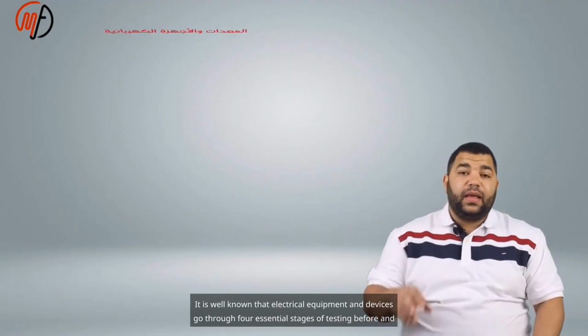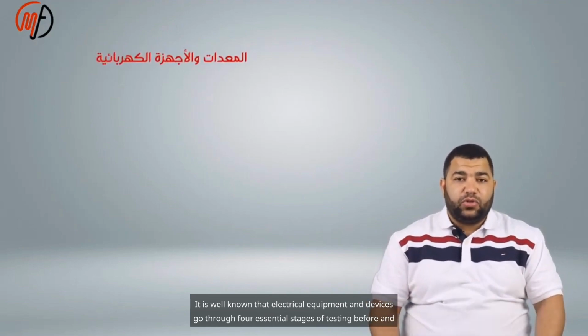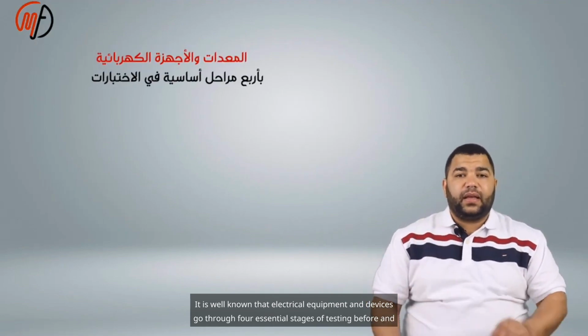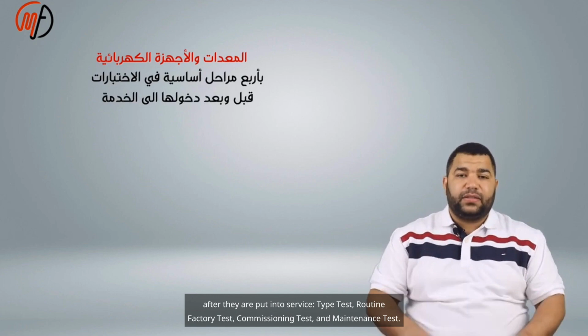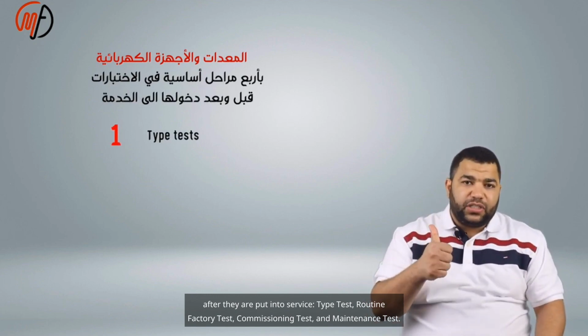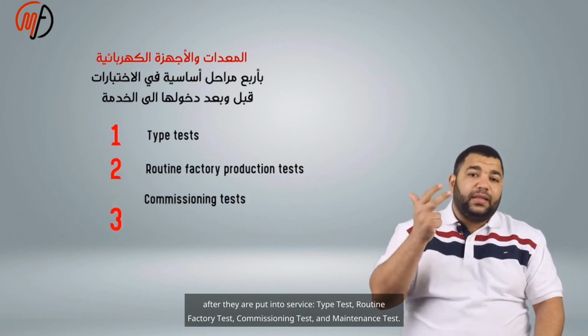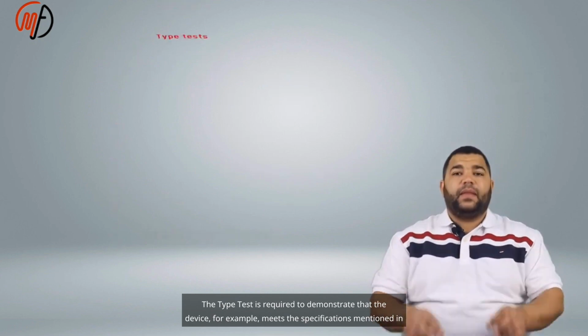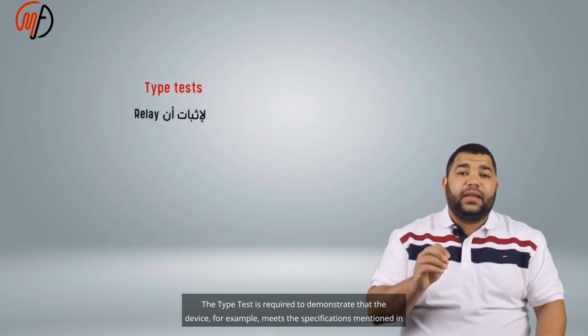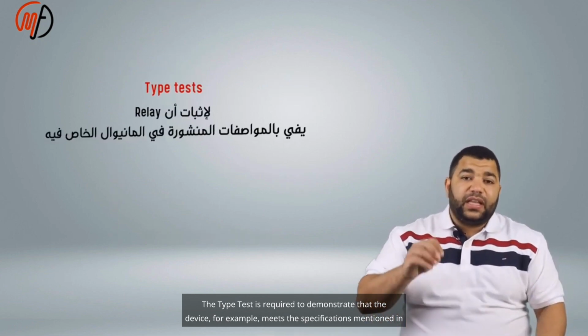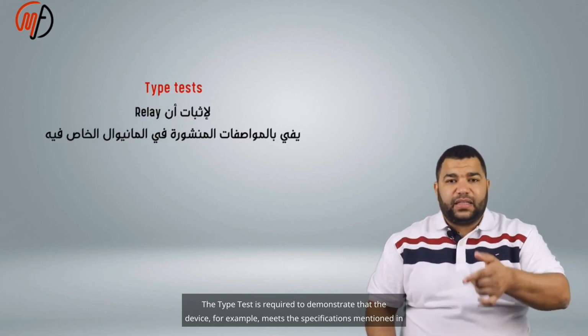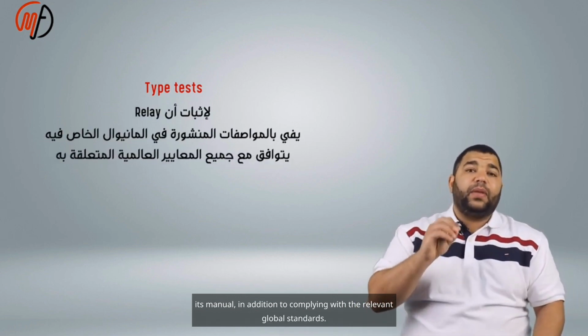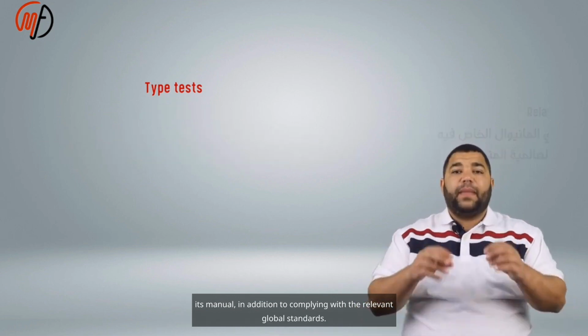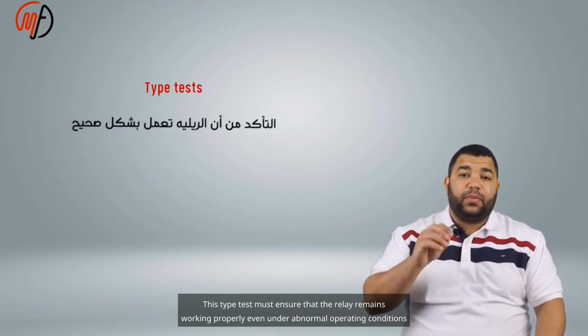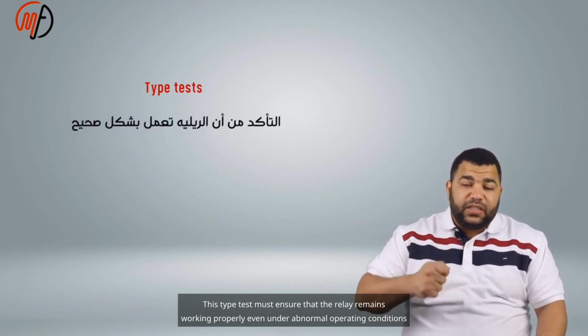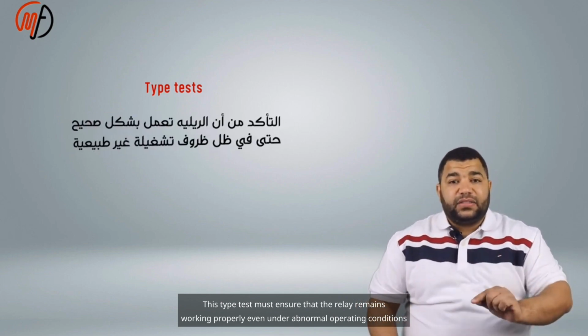It is well known that electrical equipment and devices go through 4 essential stages of testing before and after they are put into service: type test, routine factory test, commissioning test, and maintenance test. The type test is required to demonstrate that the device, for example, meets the specifications mentioned in its manual, in addition to complying with the relevant global standards. This type test must ensure that the relay remains working properly even under abnormal operating conditions according to standard IEC 60255 or IEEE C37.90.